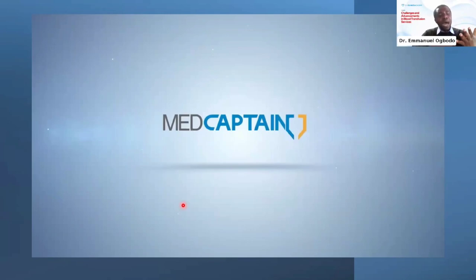Now, let's say cell 1 might have antigen D, antigen K, antigen E, antigen Duffy A, and cell 2 will have different antigens, meaning there are different antigens on each of these cells. What this analyzer is going to do is again puncture the IgG card. If it is an analyzer that uses cell 1 and cell 2, it will puncture it in two places. Cell 1 will go in the first place, cell 2 in the second place. Now remember, these cells have different antigens. Then it will use the patient plasma and put it on each of them. Again, incubate it, then centrifuge it and check it.